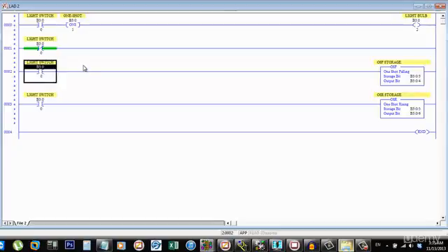When we turn the light switch off, when this condition becomes false, then we instantaneously fire our B304 bit, which lasts for one scan, and then de-energizes again, and our storage bit fires and stays energized until the light switch is closed again, in which case both of these become de-energized. So you have an extra sustained bit on your rising and falling. One works on a false to true transition, one works on a true to false transition.